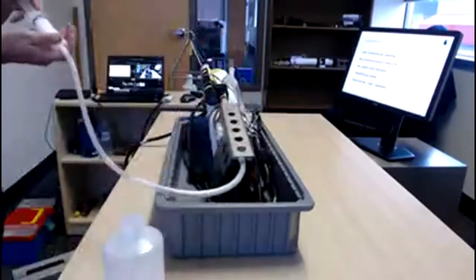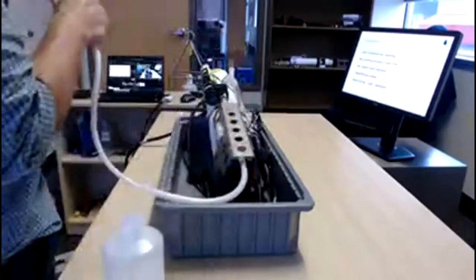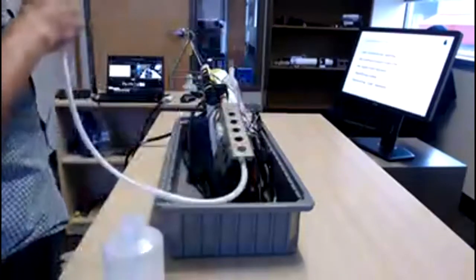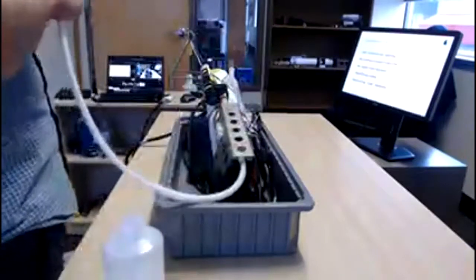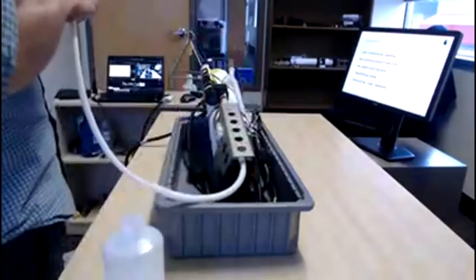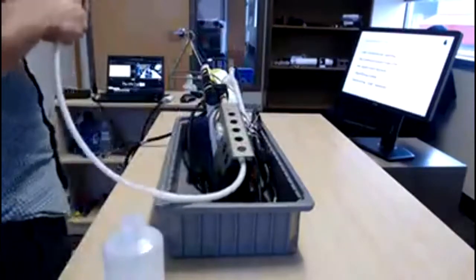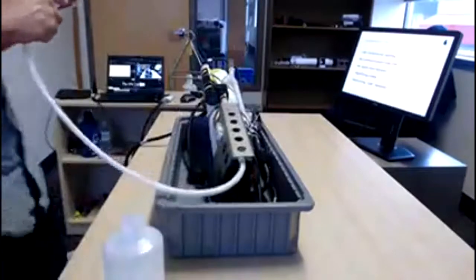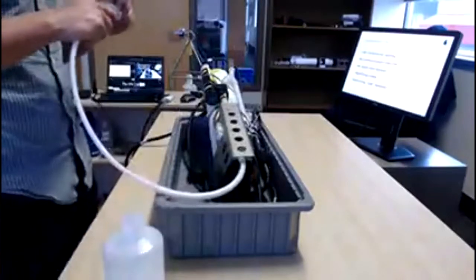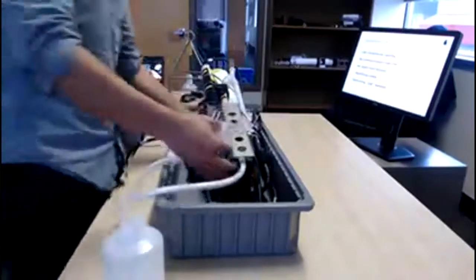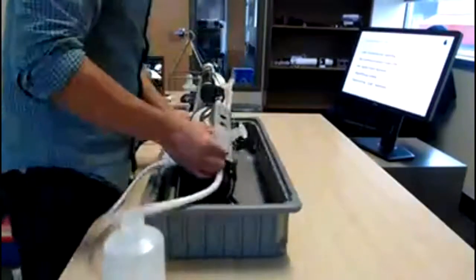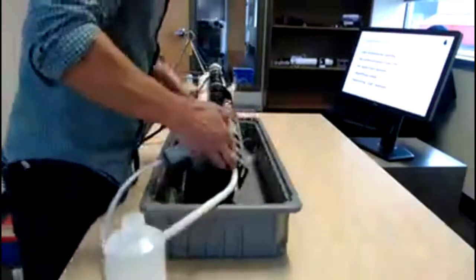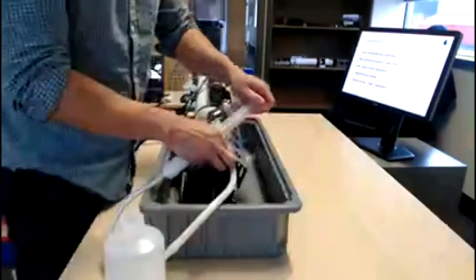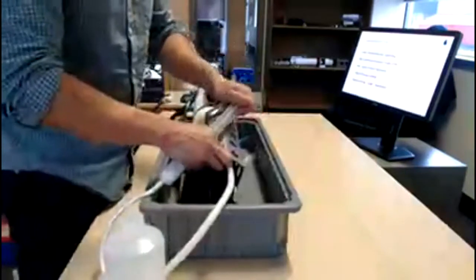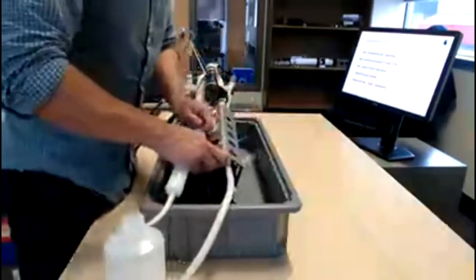What we're going to see is you get a lot of bubbles in this tubing here, and you'll see bubbles moving through your Tygon. That's good. And you're just going to want to agitate that back and forth. What this is going to do is help remove any biofouling or maybe oil that's built up inside of that. And then it's going to travel through the plumbing and out the pump. So you might need to do this a few times depending on the state of your instruments.